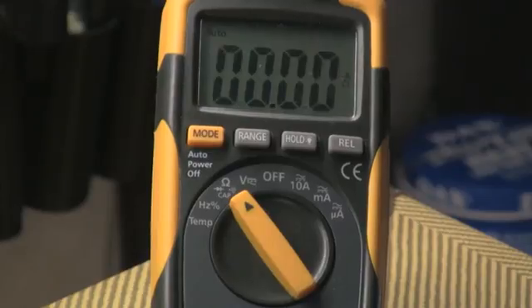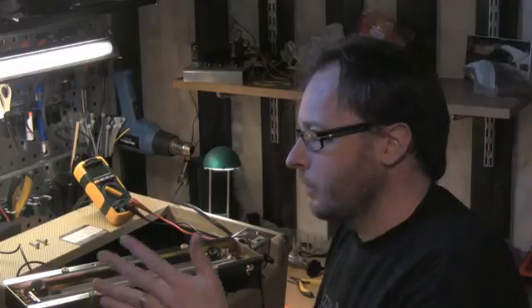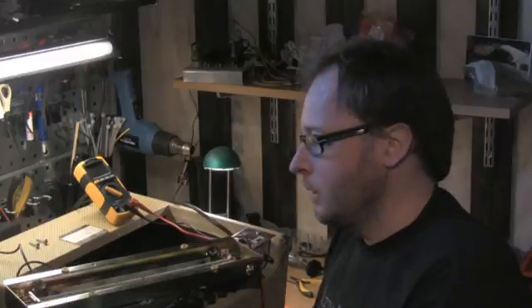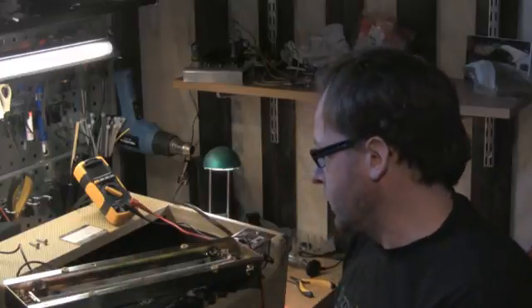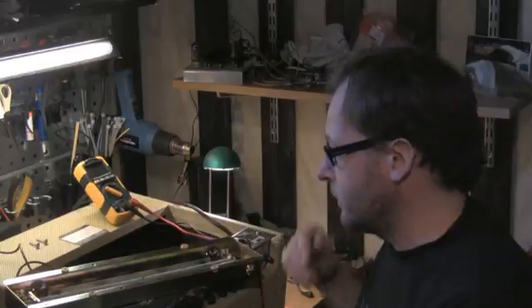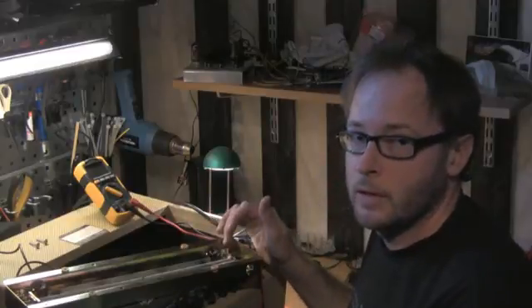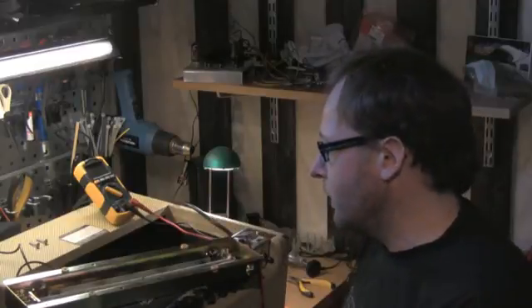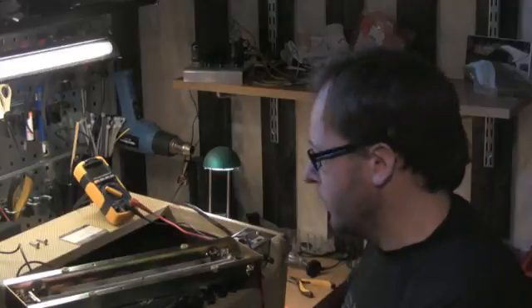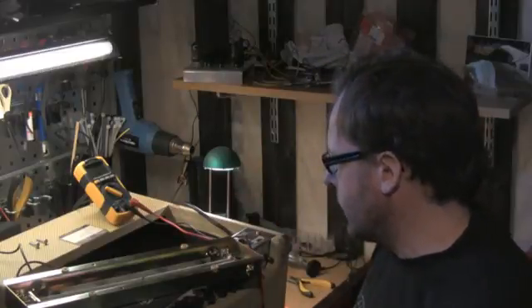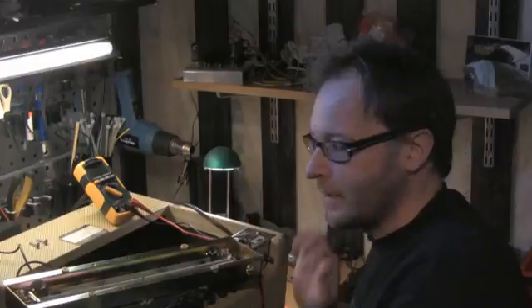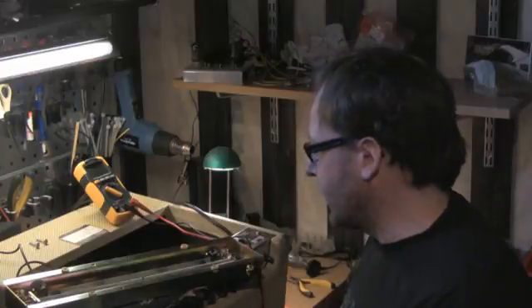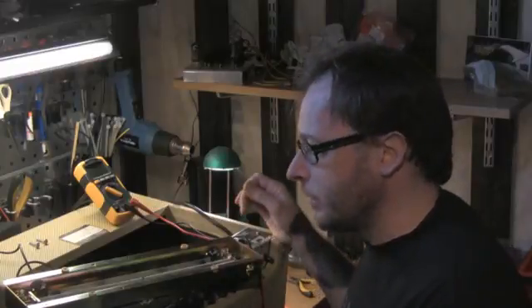When I measured the coils on the input and output side, there was around 200 ohms resistance on the output side, the pickup side, and infinite resistance - no connection whatsoever - on the input side. Here it should be around 50-60 ohms, so this transducer is blown and has to be replaced, or actually the whole tank has to be replaced. As far as I know, you can't replace just the coil.